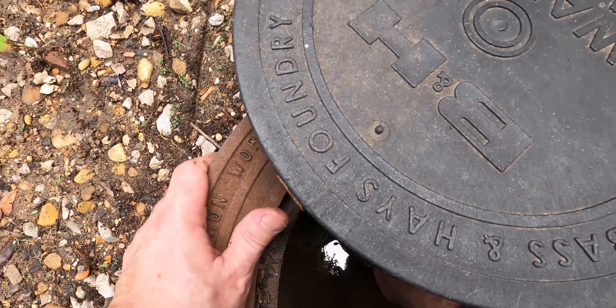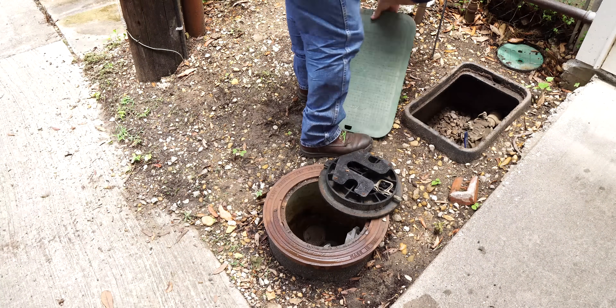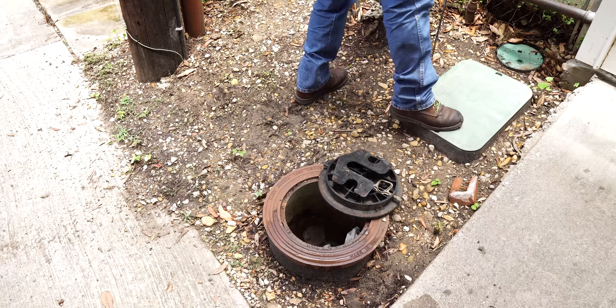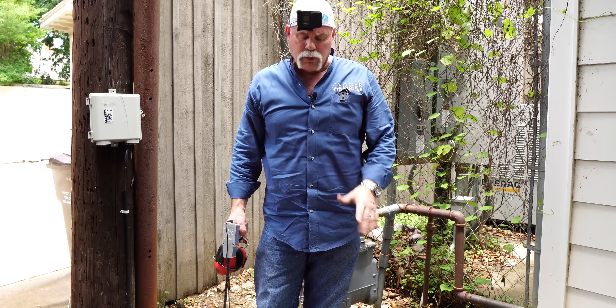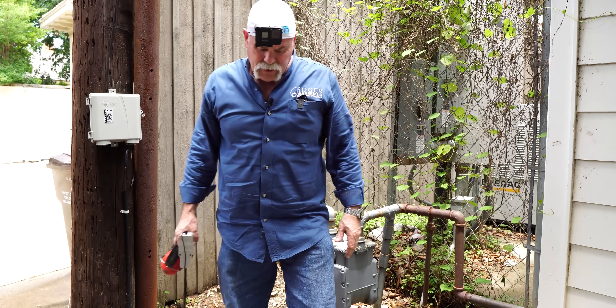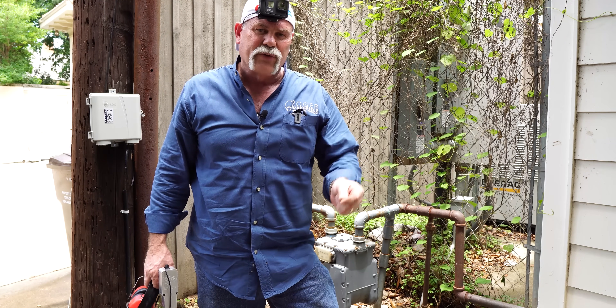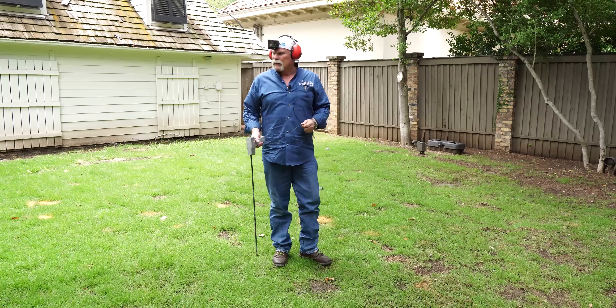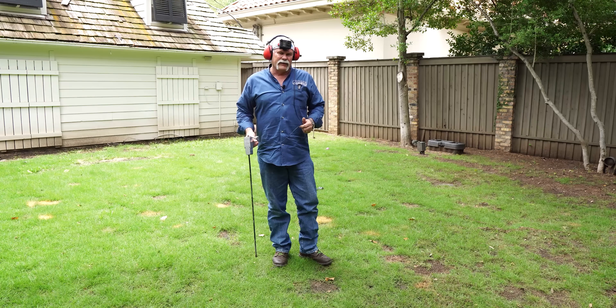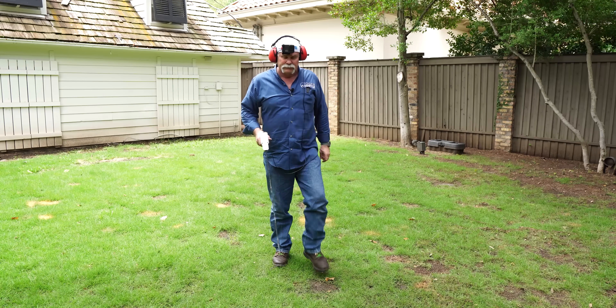Right there I'm getting a 0.33 and then back to zero. So we've watched the meter for a little bit and turned off the double check. What I'm going to do now is go up and check the house just to see if there's water there on the potable system, or if we've turned it off. Hopefully this is just turning off the irrigation, not the potable water, because all we're reading now is zeros. Whatever leak is here is tiny — it's showing zeros time after time, but then all of a sudden you get a 0.33, showing us there is a little bit of water movement.